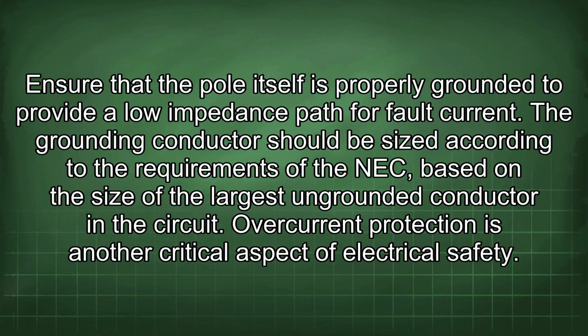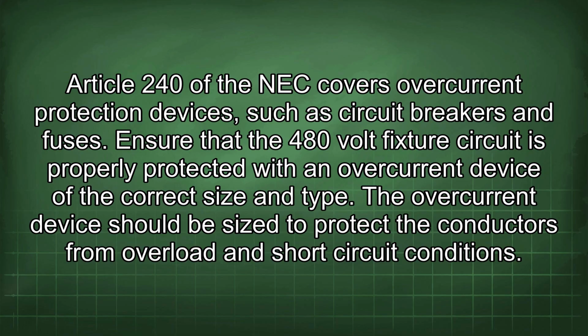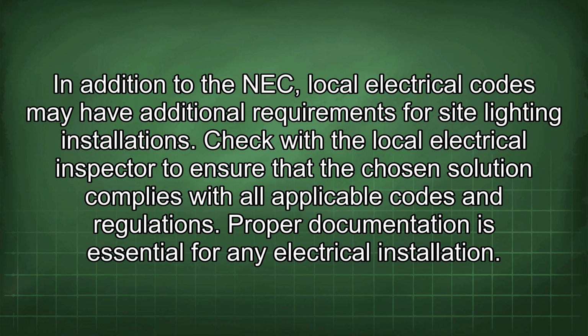Overcurrent protection is another critical aspect of electrical safety. Article 240 of the NEC covers overcurrent protection devices, such as circuit breakers and fuses. Ensure that the 480-volt fixture circuit is properly protected with an overcurrent device of the correct size and type. The overcurrent device should be sized to protect the conductors from overload and short-circuit conditions. In addition to the NEC, local electrical codes may have additional requirements for site lighting installations. Check with the local electrical inspector to ensure that the chosen solution complies with all applicable codes and regulations.